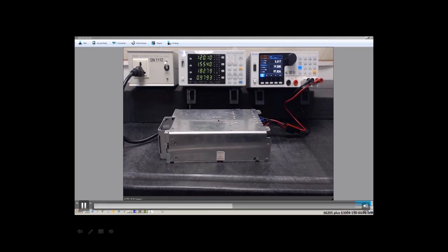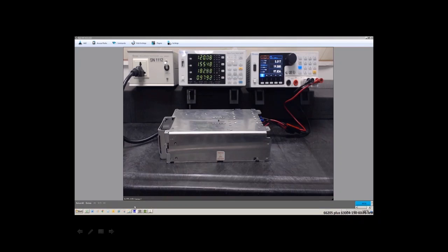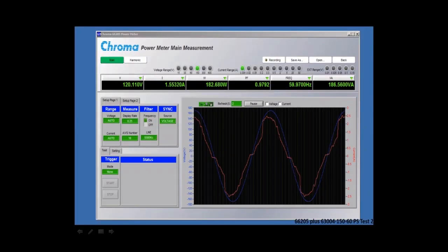The other thing about this particular power meter here is that I mentioned we use multiple different interfaces. It comes with a standard USB and has Ethernet and GPIB options. We can also interface it to our software through your laptop or your PC, and I happen to have our software running. This is a live view of our software, and in this particular screen I'm measuring 6 different measurements across the top.